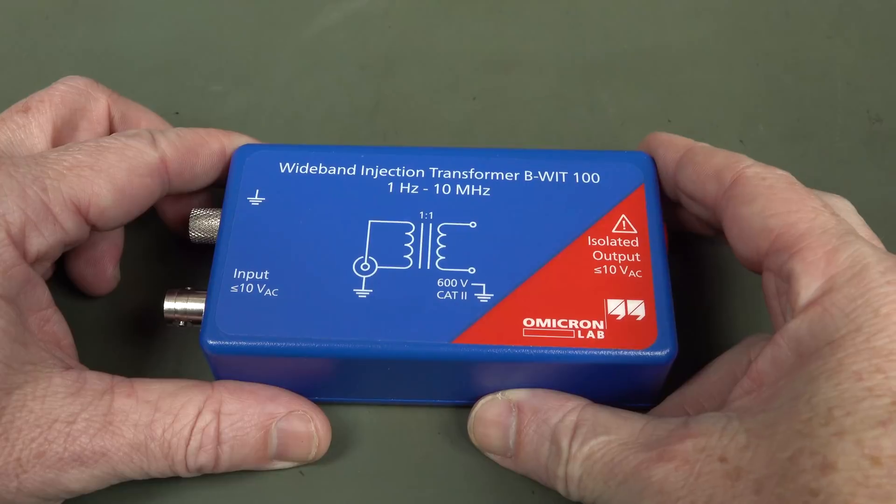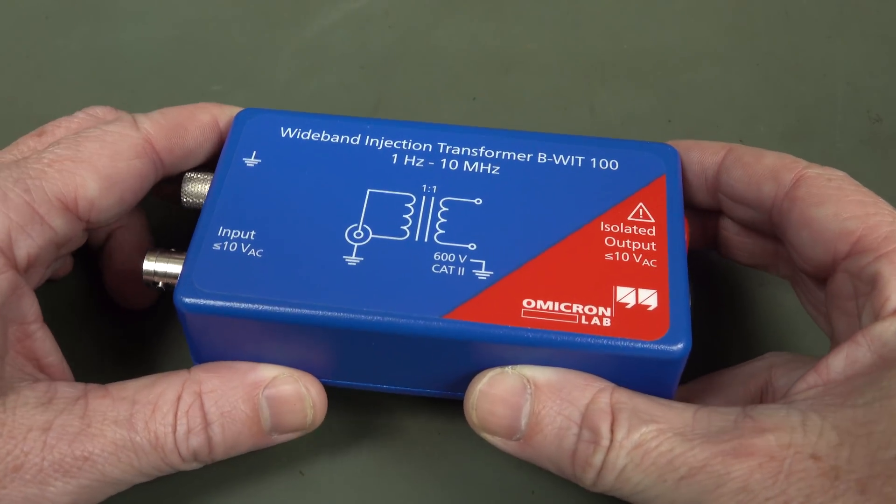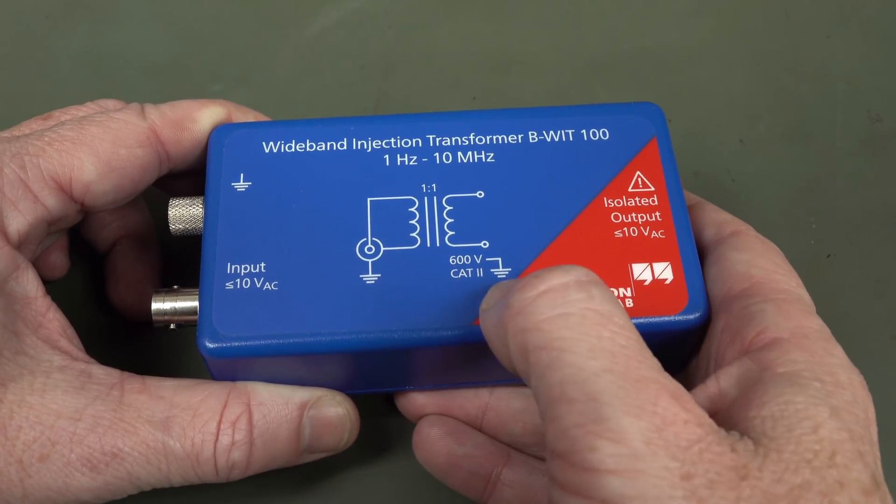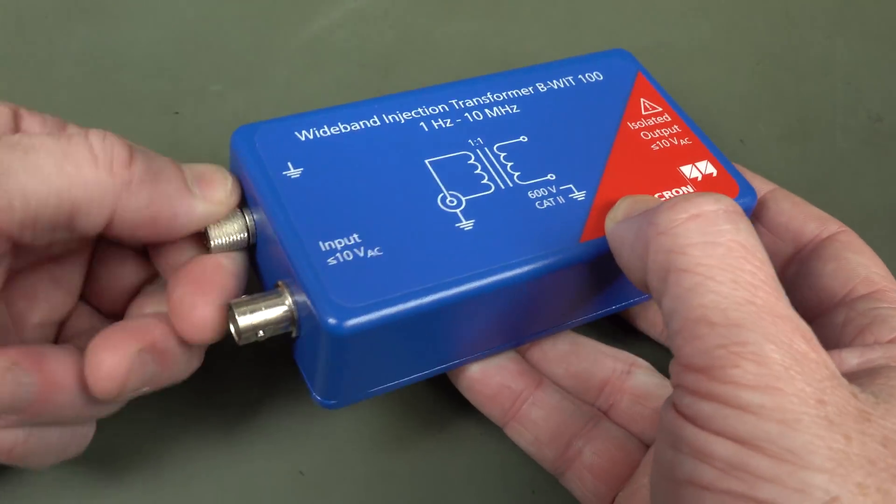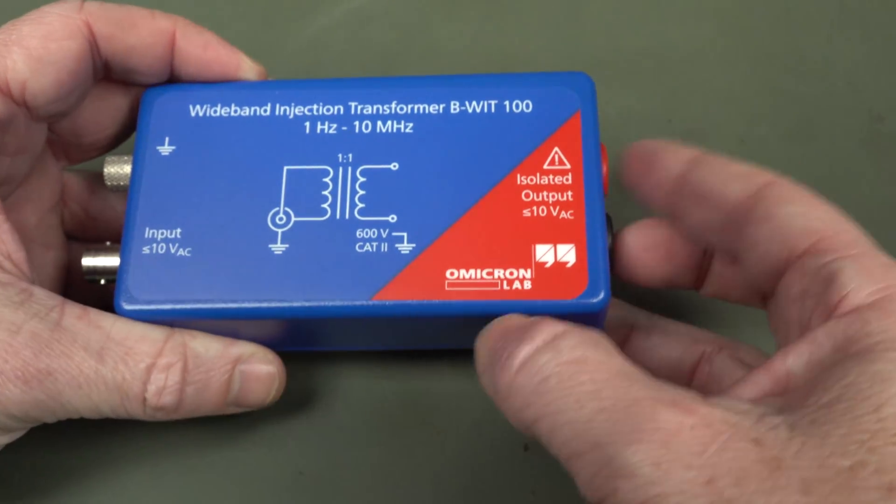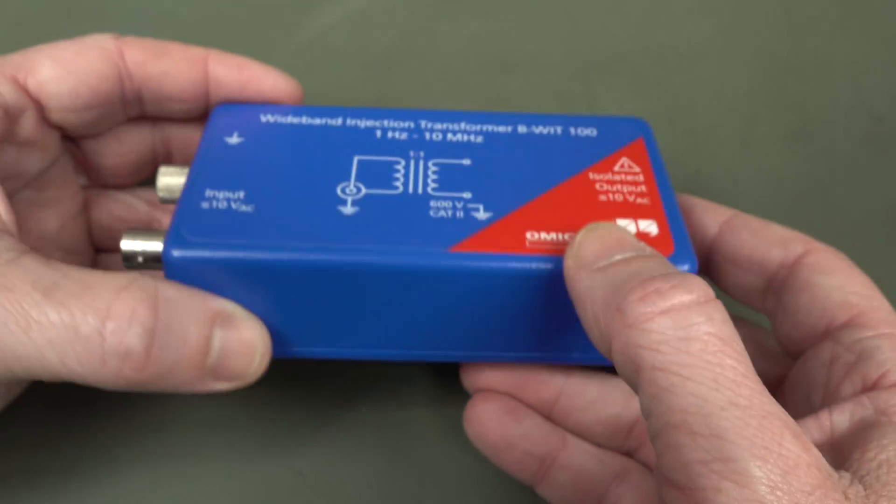I want to do this first, so we've got the BWIT 100, 1 hertz to 10 megahertz wideband injection transformer. It's just a 1 to 1 transformer, 600 volt CAT 2 isolation, just BNC input, just the earth terminal which would just be the outer case here and just banana plugs, a balanced output on this side, isolated. So let's take a look.